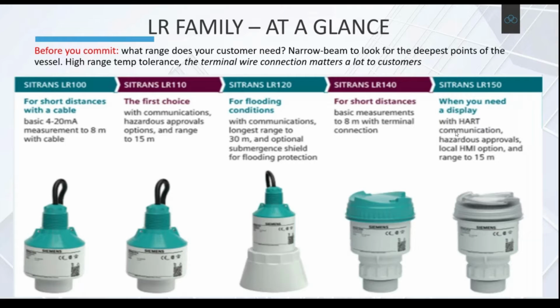If you wanted a hazardous one for a hazardous area, like diesel or fuel oil level, then you would go for the LR150 or the LR110. It depends on how you're mounting it. If you're screwing it into a vessel, you might want something with a threaded end to screw into the vessel itself. Or if you wanted to mount it over an open wall, then you could use something like the LR100 or the LR110, which can be mounted, hung like a chandelier almost.